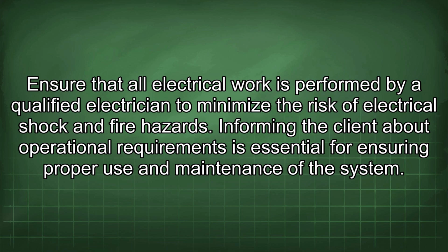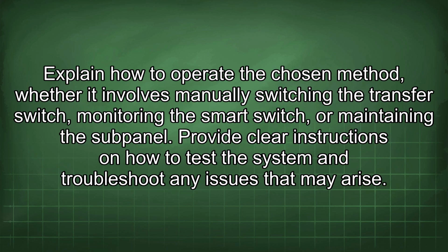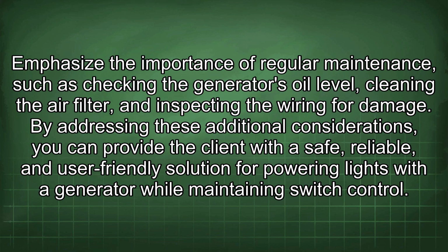hazards. Informing the client about operational requirements is essential for ensuring proper use and maintenance of the system. Explain how to operate the chosen method, whether it involves manually switching the transfer switch, monitoring the smart switch, or maintaining the subpanel. Provide clear instructions on how to test the system and troubleshoot any issues that may arise. Emphasize the importance of regular maintenance, such as checking the generator's oil level, cleaning the air filter, and inspecting the wiring for damage. By addressing these additional considerations, you can provide the client with a safe, reliable, and user-friendly solution for powering lights with a generator while maintaining switch control.